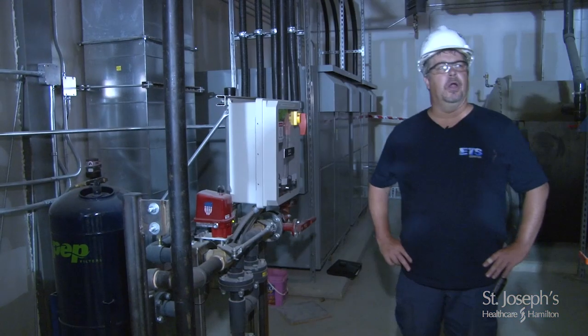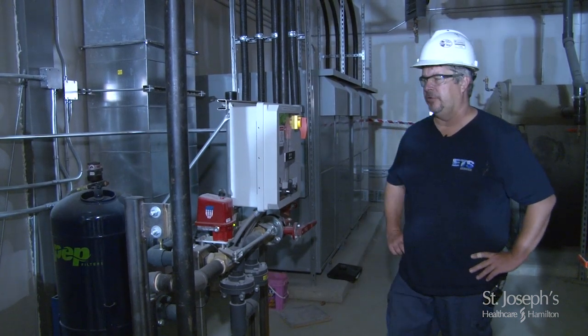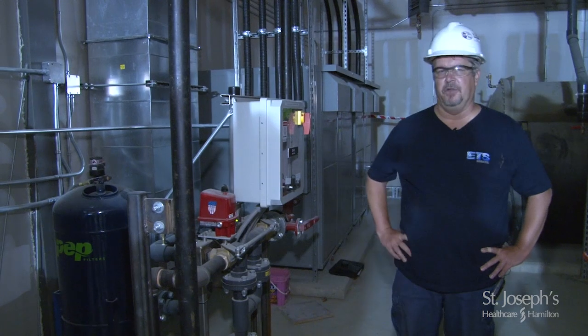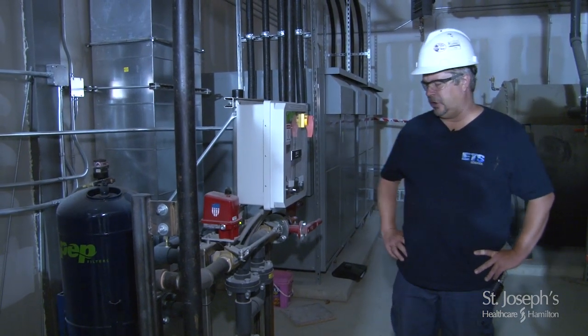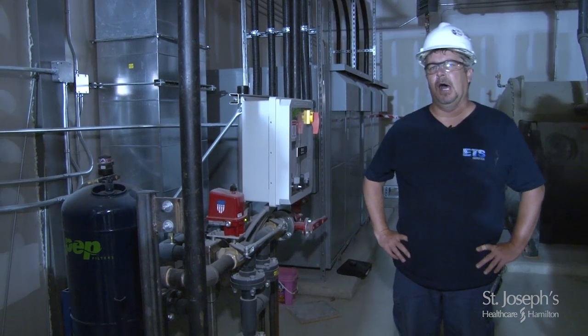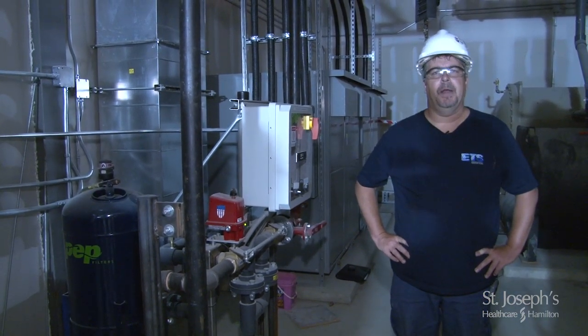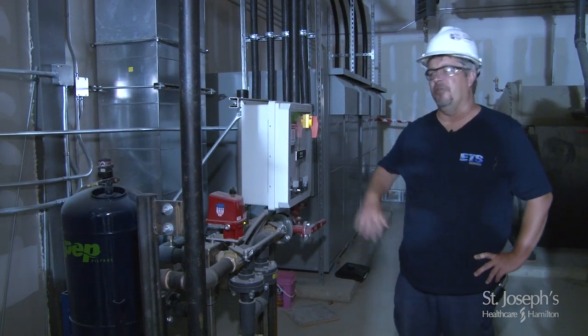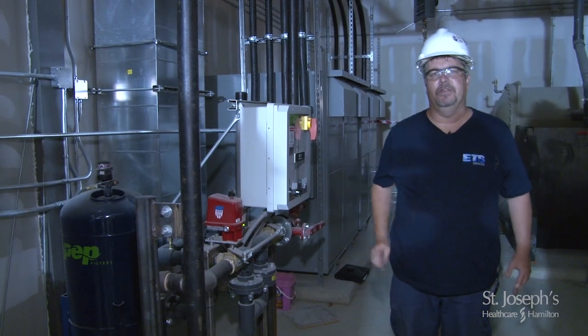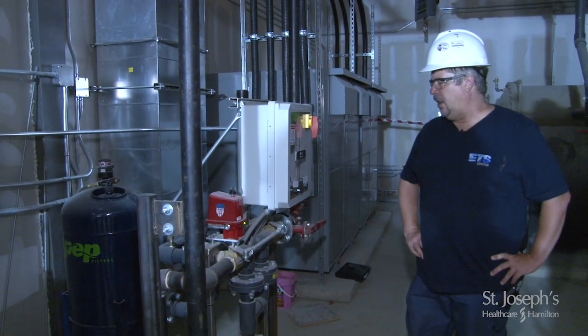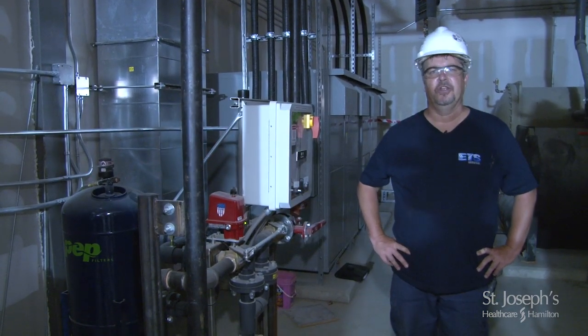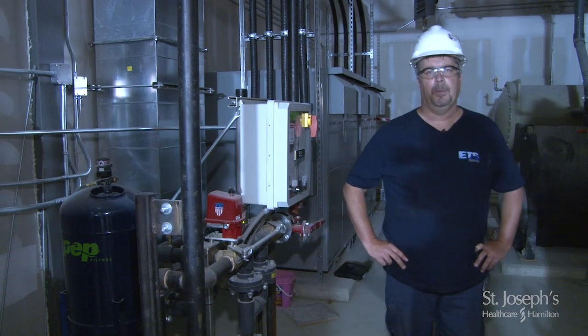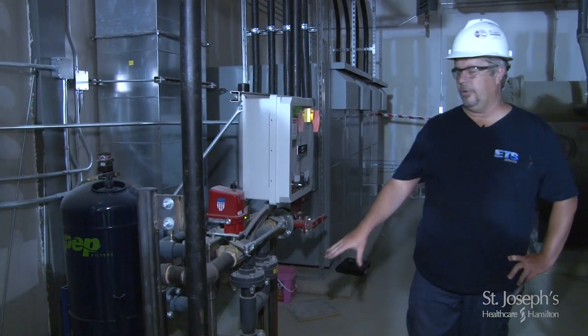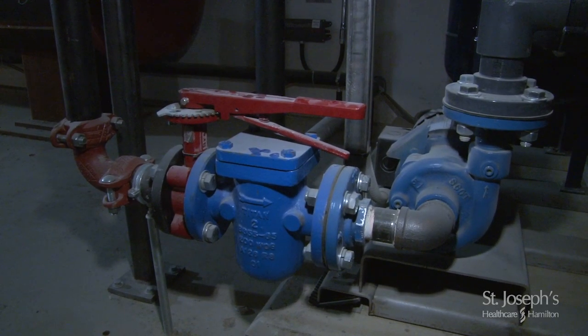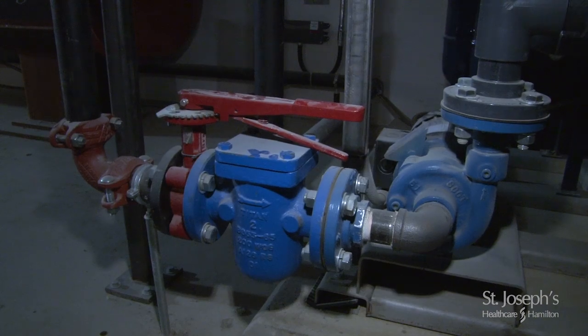We are currently standing in the mechanical room of St. Joseph's Hospital. We're about to talk about the PEP sand filter. This sand filter is designed and used in conjunction with the cooling towers to filter any sediment that might happen to get washed in or through the cooling tower before it reaches the chiller and causes any damage inside the chiller. The simplest way to think about how this filter functions is if you think of a filter on a swimming pool. You basically have the water entering the tower through a pump system, which you can see down right here. That pump then sends the water up and through an actual filter media.